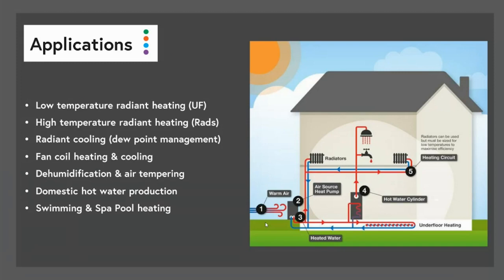Those are basically like your air conditioner type things. They have a coil in them that has hot or cold water running through it, and then a fan that can blow that into the room. And those can be used in combination with radiant systems. For example, you could have underfloor heating on a ground floor, and then you could have fan coils on the upstairs because that area might need some cooling in the summer, and that can all be connected to the same system. These systems can also be used for dehumidification and air tempering in heat recovery units.